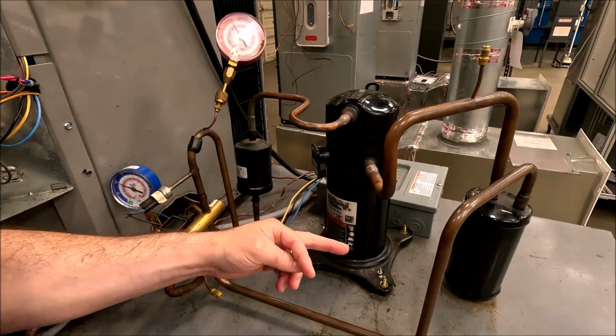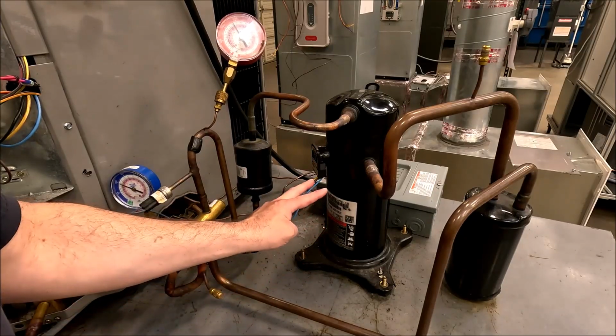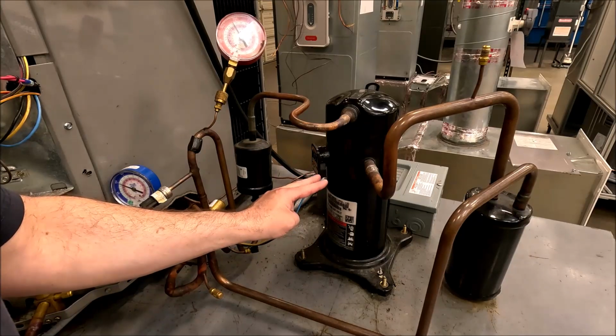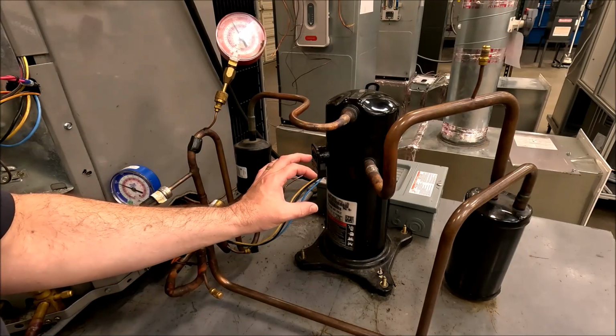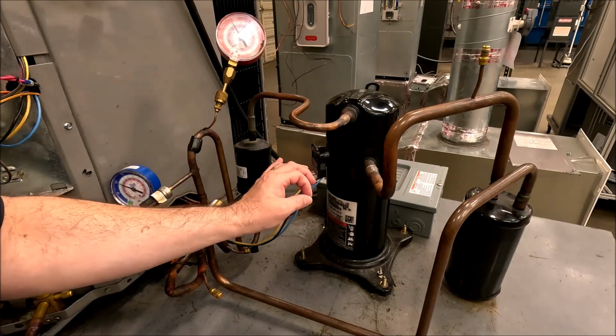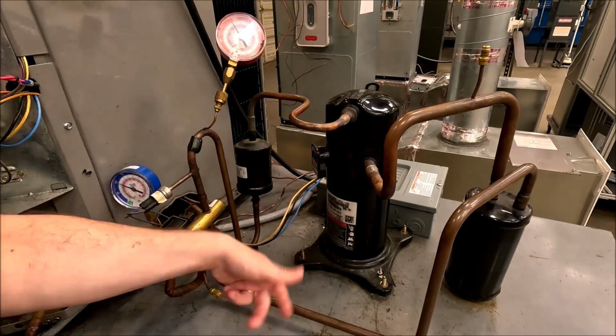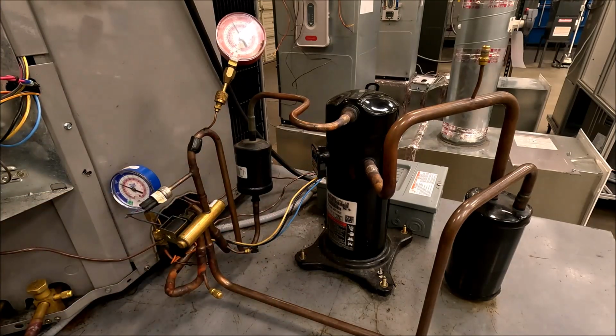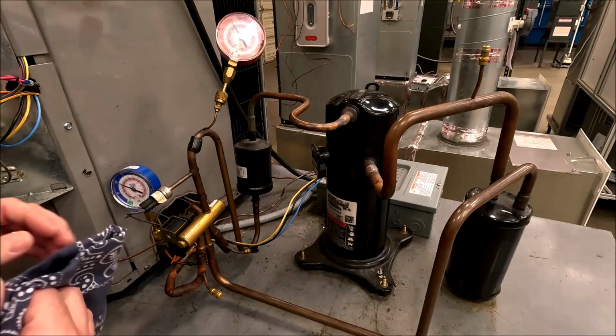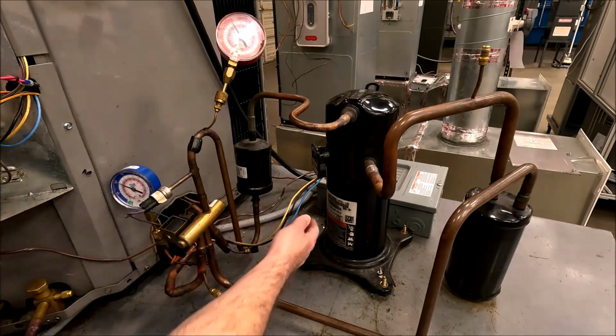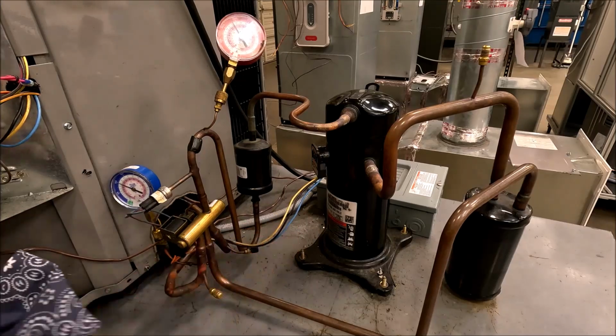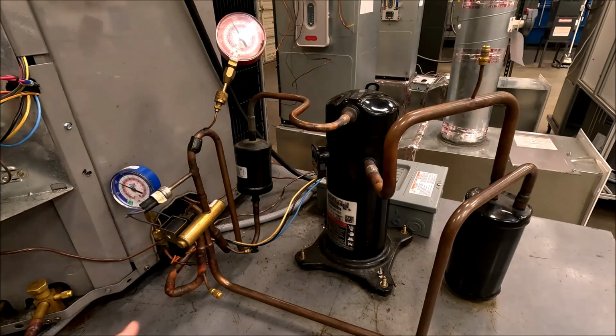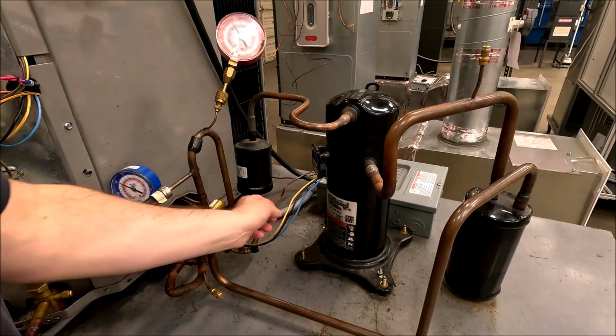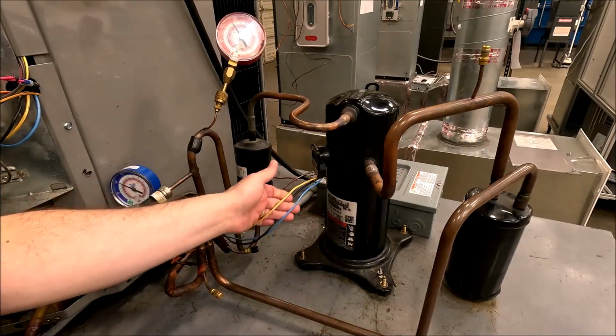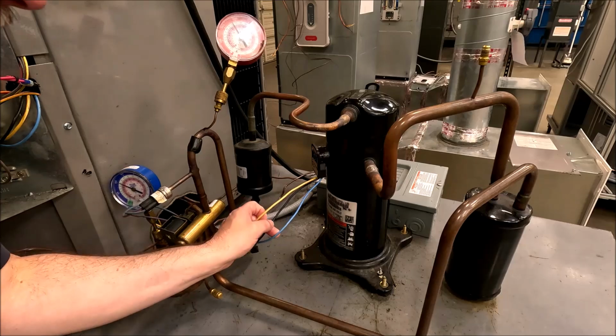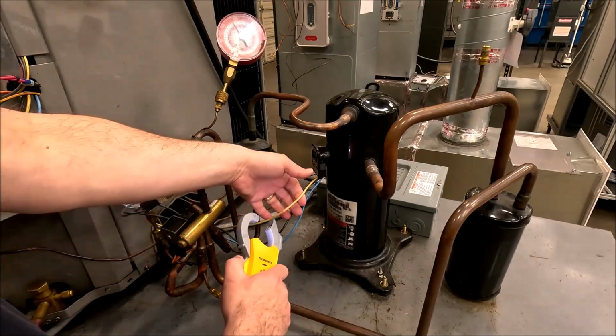Run and start, the R and the S, they go into their respective winding, and they both meet on one end, and that's the common terminal. And you probably have an overload in there, some type of temperature safety. But the common, this wire is not for a winding. It is strictly a one-way road back from these 2. All right. So watch this. We're gonna check the run.